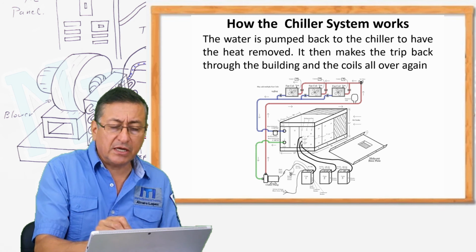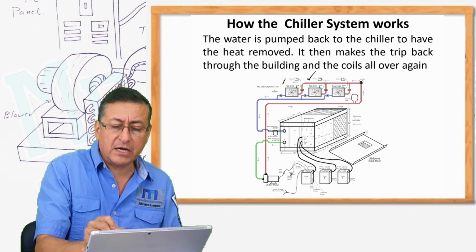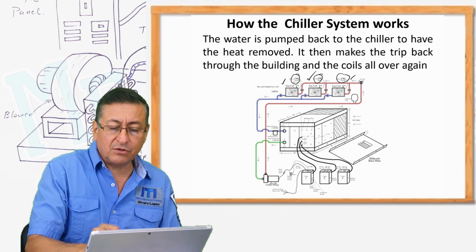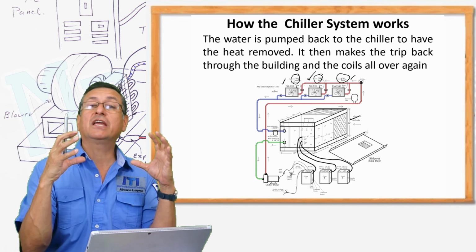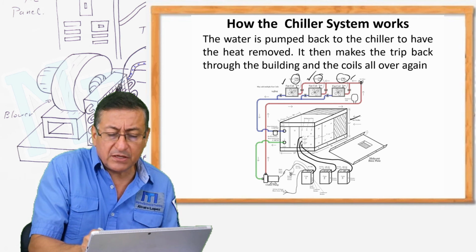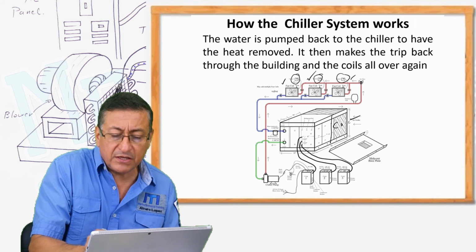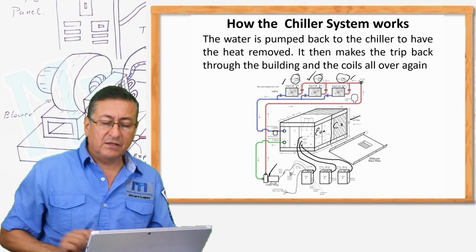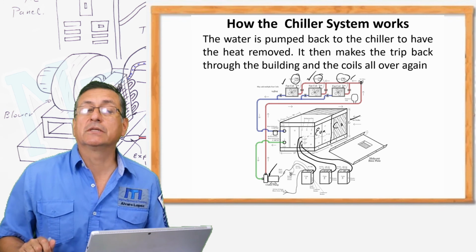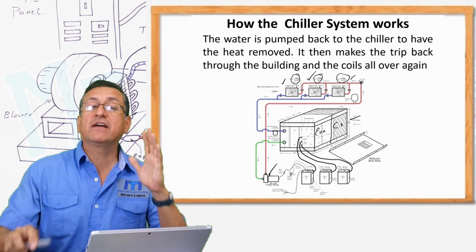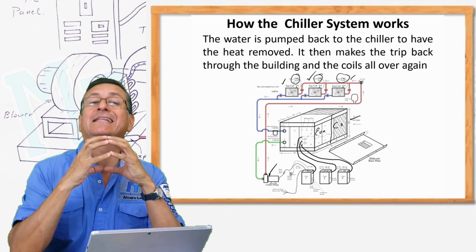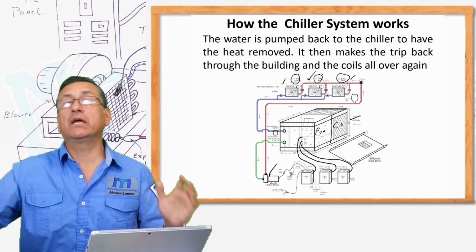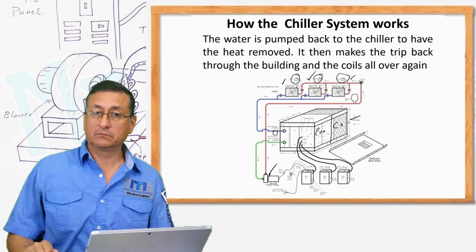Look, in this particular case, we have 3 air handlers with 3 thermostats. And this is the container where the self-contained unit is located. Half of this is the condenser and half of this is the evaporator. And this is the circulating pump for the freshwater system. Remember, in the chiller system we have two pumps. One pump to circulate the chilled water, and another pump to circulate the raw water for the condenser.